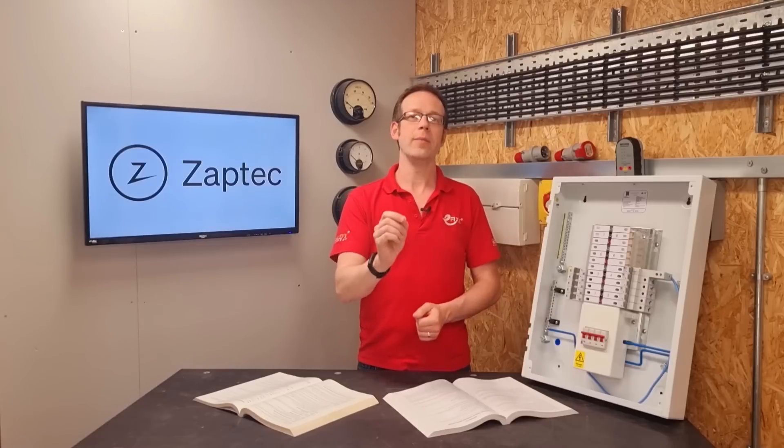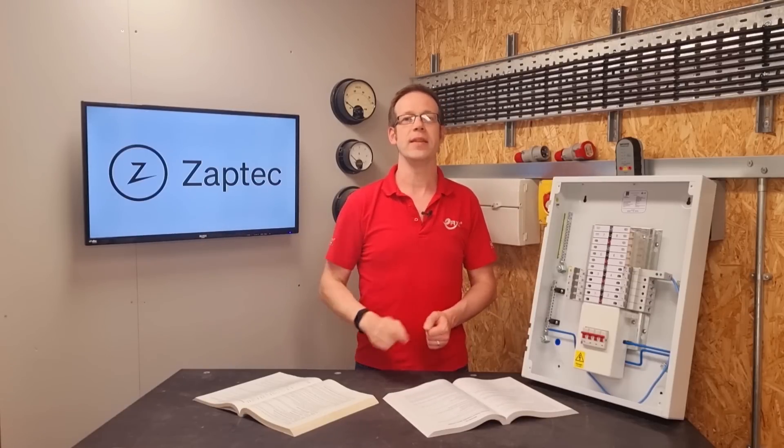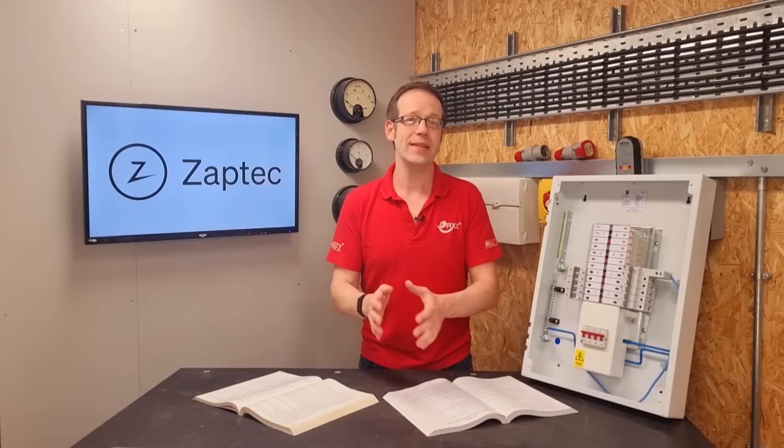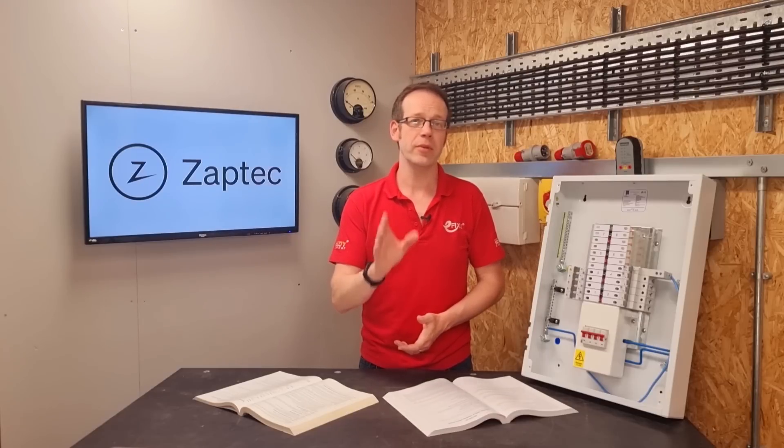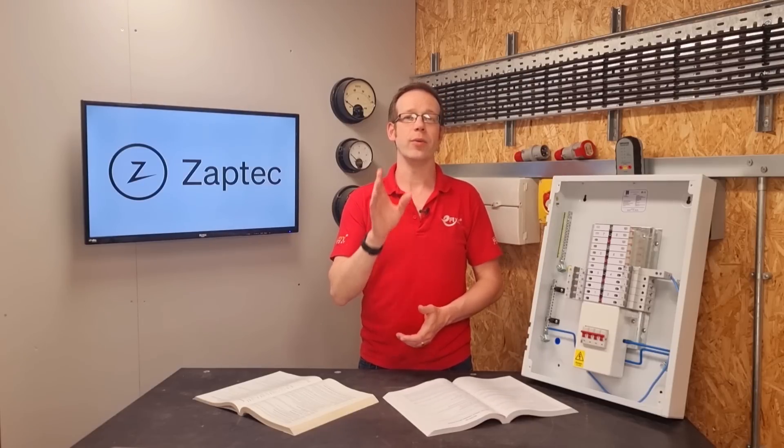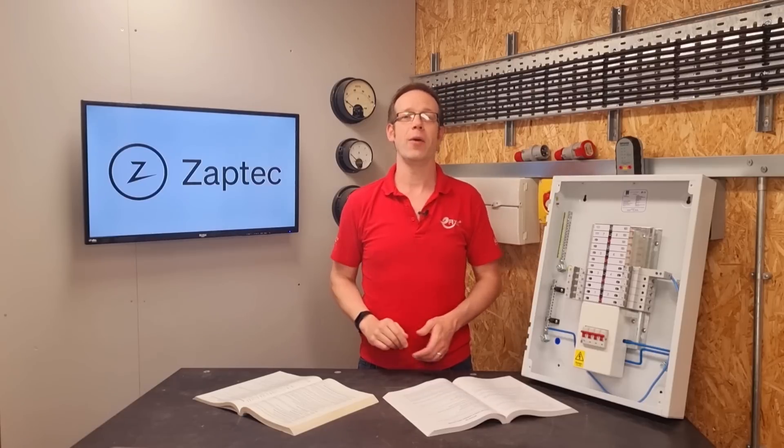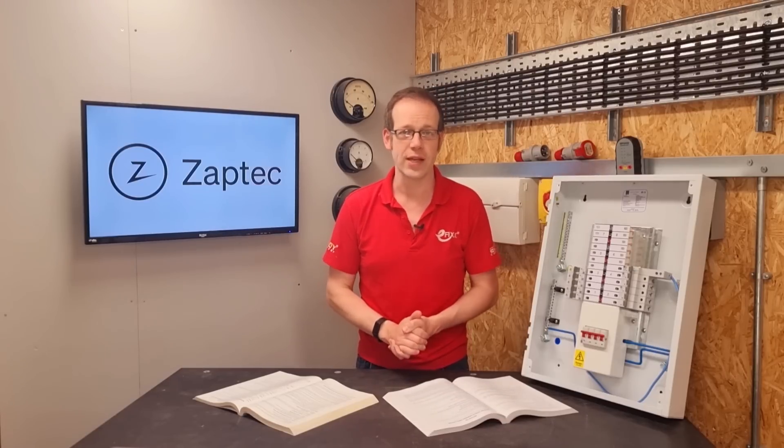And that I believe is the reason that if we look at that same regulation in the second amendment to the 18th edition, you'll notice that this option in indent one has been deleted. Which means that from the 27th of September 2022 onwards you'll no longer be able to rely on the charge point being connected to a three-phase system as protection enough, and you'll need to carry out one of the options from indents two to five to provide PEN fault protection.